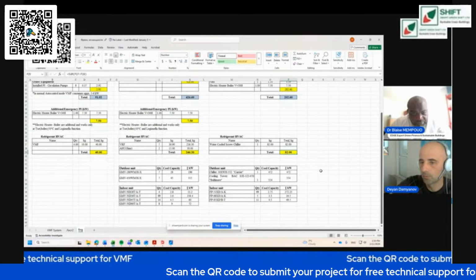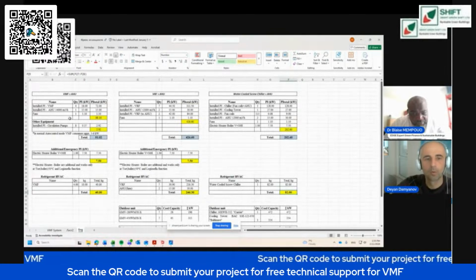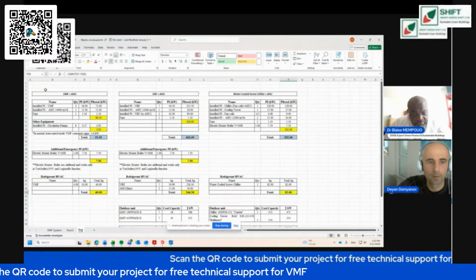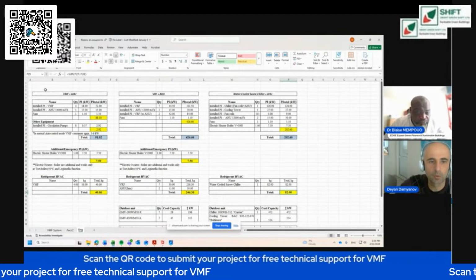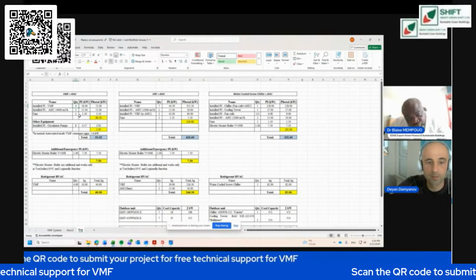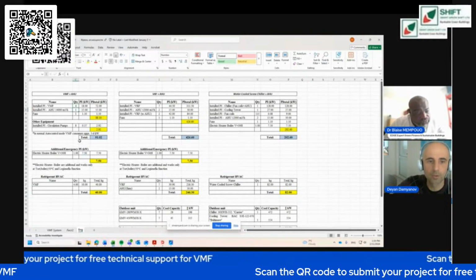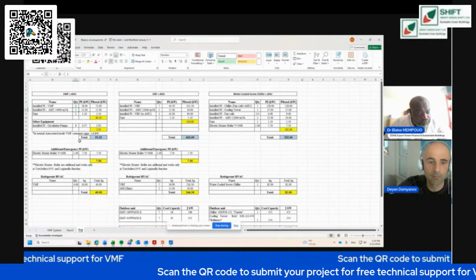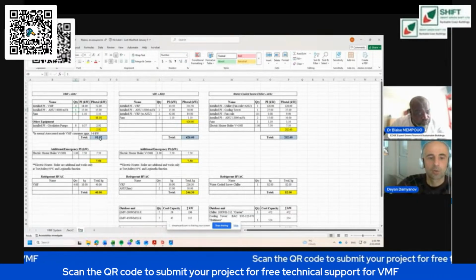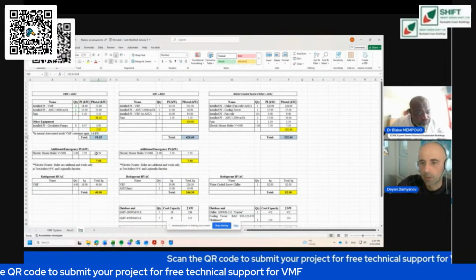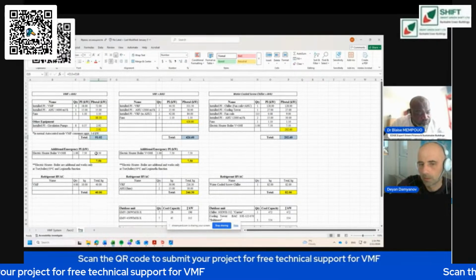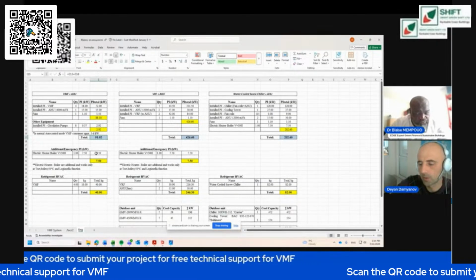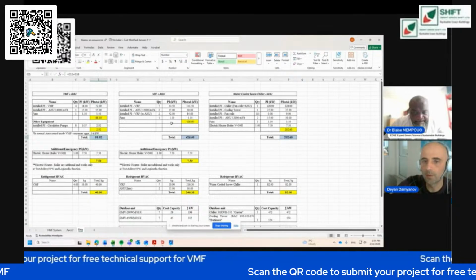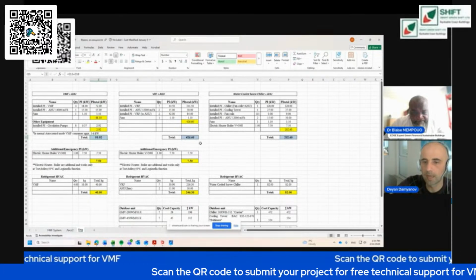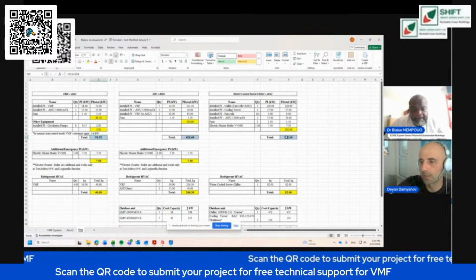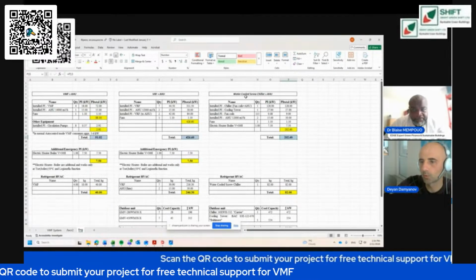At 82 kilograms. But when we go to our concept of VMF, on this project we have 4 pieces of VMF in total plus 1 additional air handling unit with heat recovery. Our total installed electric power is 91 kilowatts, which is a huge difference compared to the VRF plus air handling units — more than 4 times smaller, and more than 2 times smaller than the water-cooled screw chiller option.